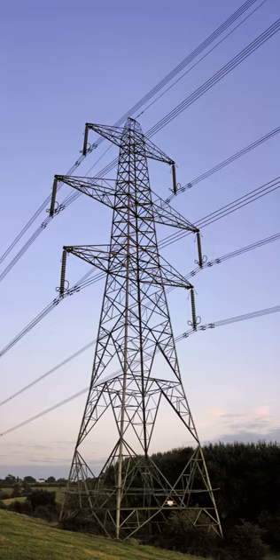in use. In the latter case, the line from the converter station to the earthing grounding electrode is built as underground cable, as overhead line on a separate right-of-way or by using the ground conductors. Electrode line towers are used in some HVDC schemes to carry the power line from the converter station to the grounding electrode. They are similar to structures used for lines with voltages of 10 to 30 kV, but normally carry only one or two conductors.